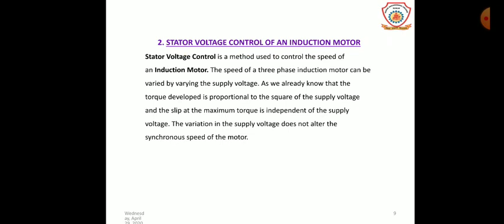The stator voltage control method is used to control the speed of an induction motor. The speed of a three-phase induction motor can be controlled by varying the stator voltage, which is varied until the torque required by the load is developed at the desired speed. The torque developed is proportional to the square of the supply voltage, and the current is proportional to the voltage. To reduce speed, the voltage is reduced, which reduces the torque. An example of this method is fan load.